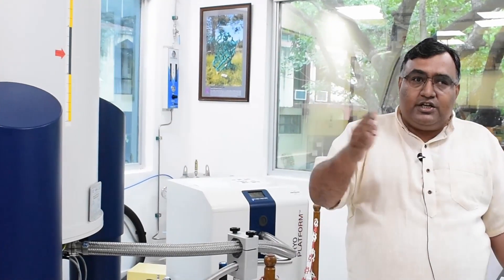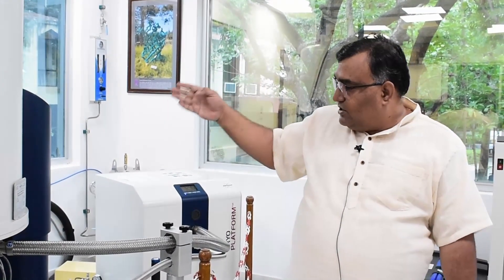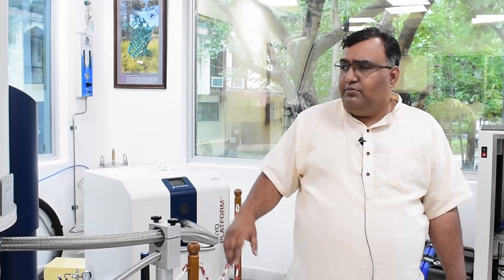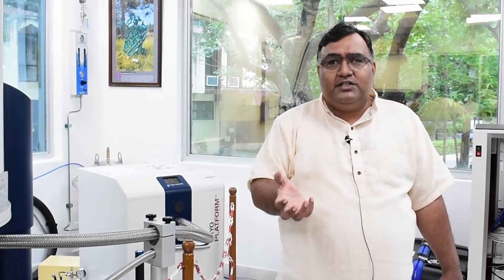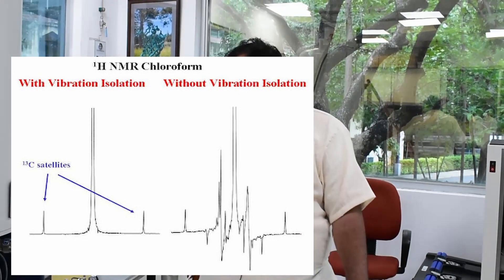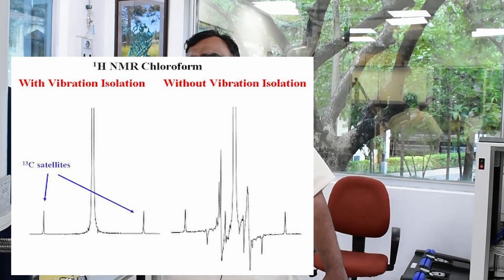So during the experiment if you have such kind of oscillations and your magnet instead of at 14.1 Tesla, the last digits get changed, your magnetic field, the sample is experiencing will also not be uniform. Because it won't be uniform, your signal will become broad. So you won't be able to detect reasonable data.